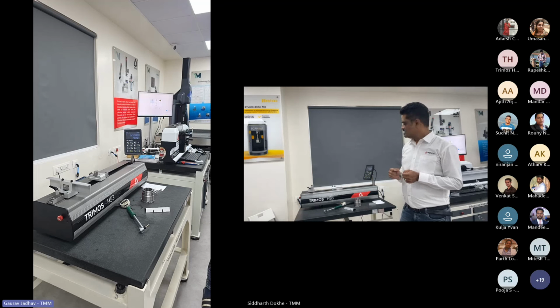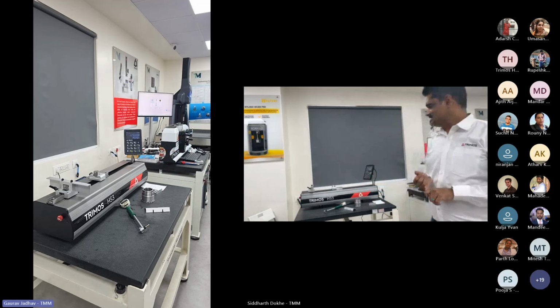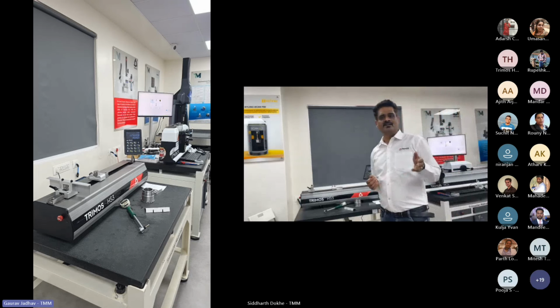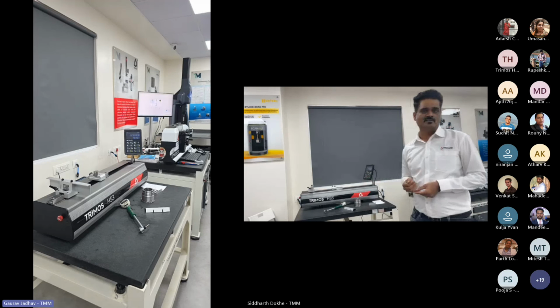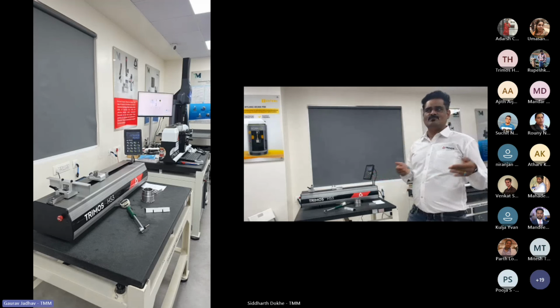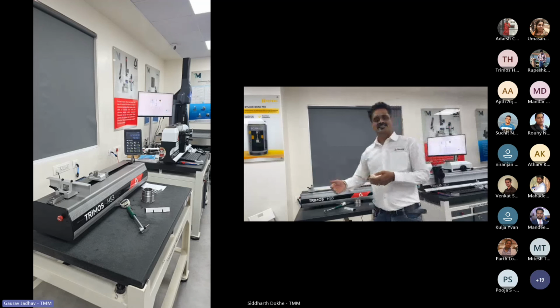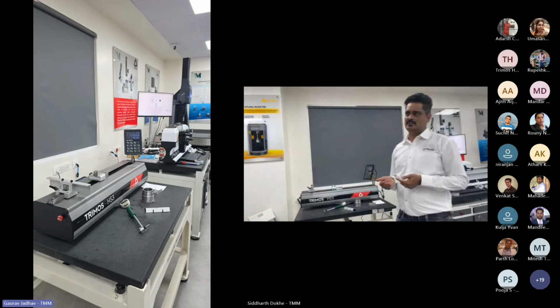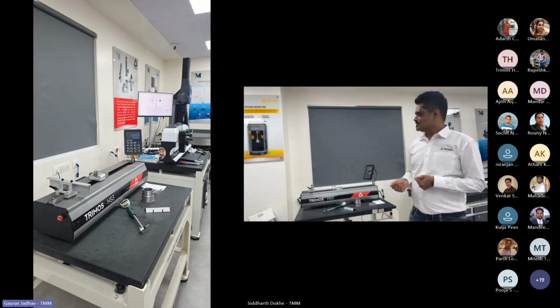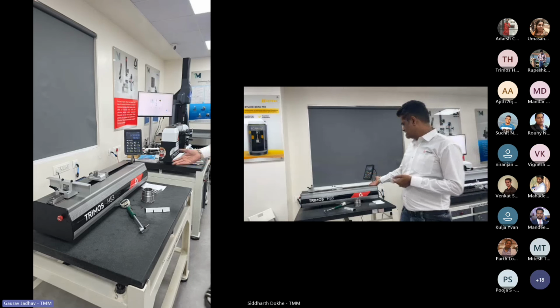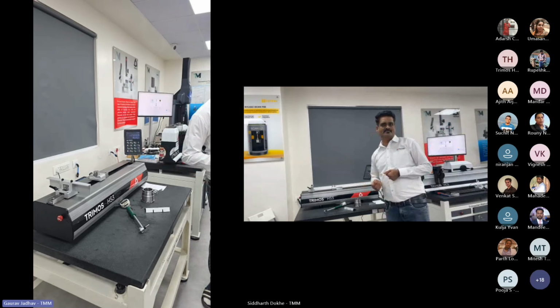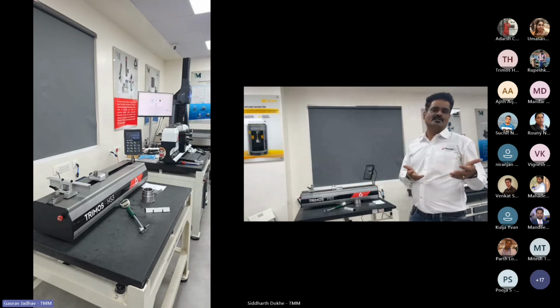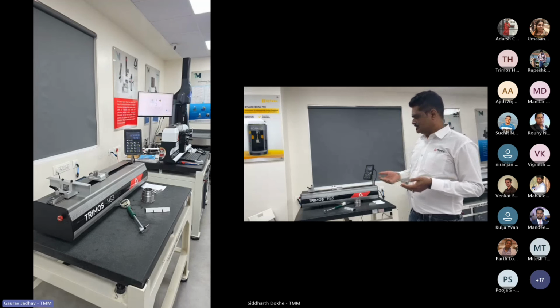reading. The repeatability of this machine is 0.5 micron, and as I said, the maximum permissible error is 0.7 micron plus L by 1000. So the entire range is 1.1 micron maximum permissible error. The machine will come exact within half of the accuracy limits. So when you purchase a new machine, you can see the calibration certificate. It will be within 0.5 to 0.6 micron. You will get this machine.